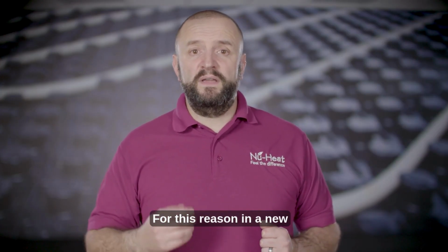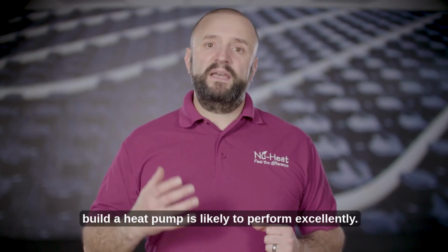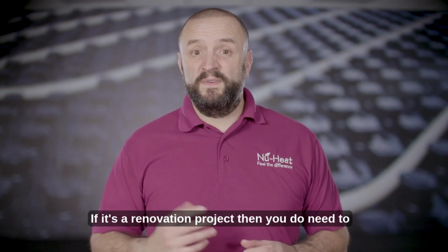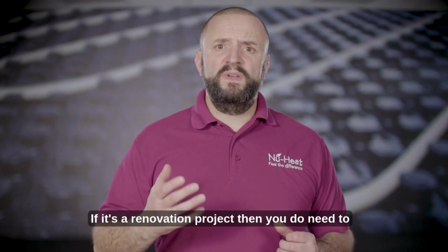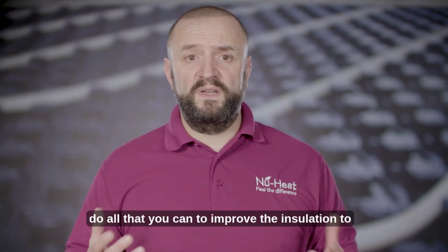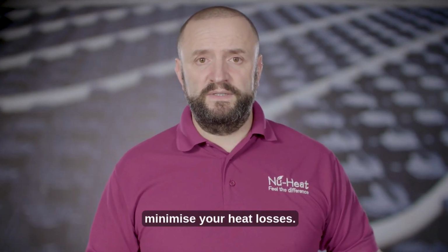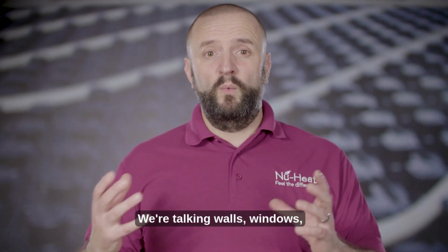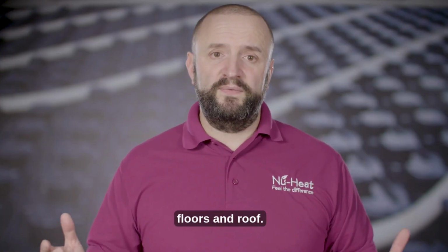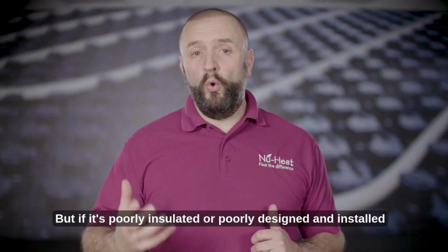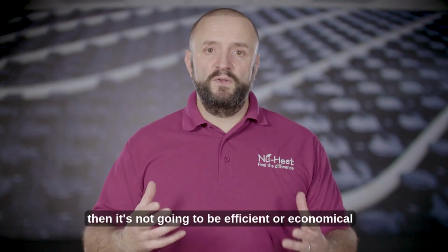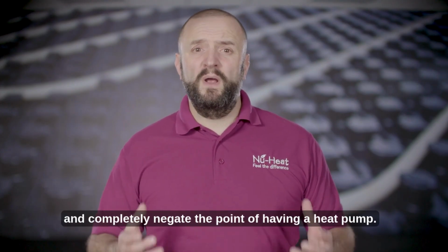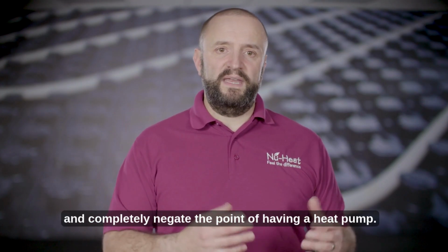For this reason, in a new build, a heat pump is likely to perform excellently. If it's a renovation project, then you do need to do all that you can to improve the insulation to minimise your heat losses. We're talking walls, windows, floors and roof. But if it's poorly insulated or poorly designed and installed, then it's not going to be efficient or economical and completely negate the point of having a heat pump.